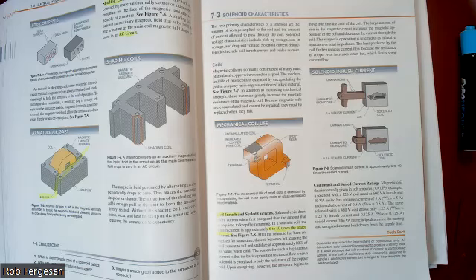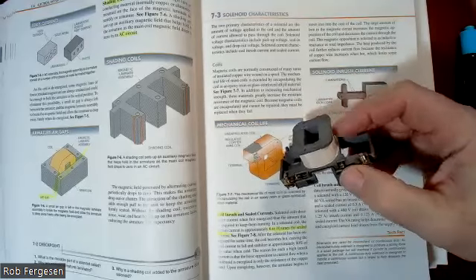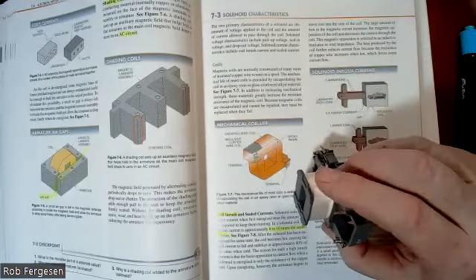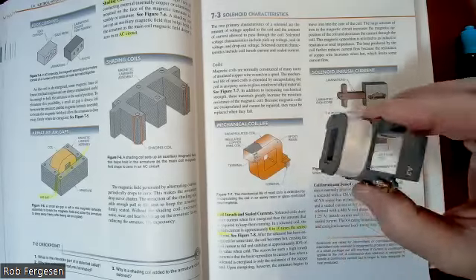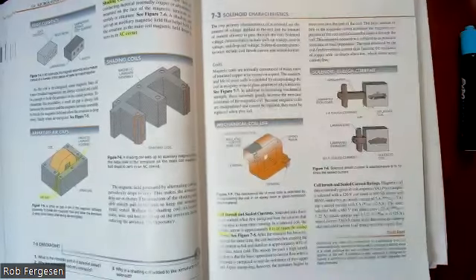So you have to look at the specifics of the coil. In the case of this coil, this has a high temperature nylon wrapped around it to protect it. And that's a higher dollar coil, and that will last longer in an industrial environment. It's designed for a contactor.